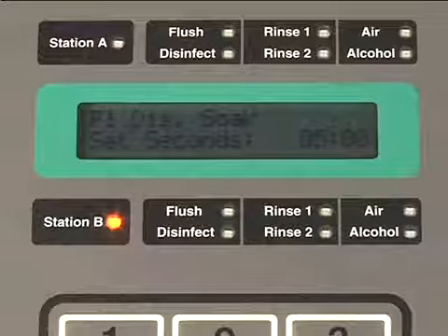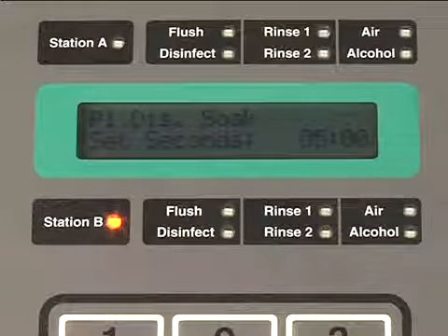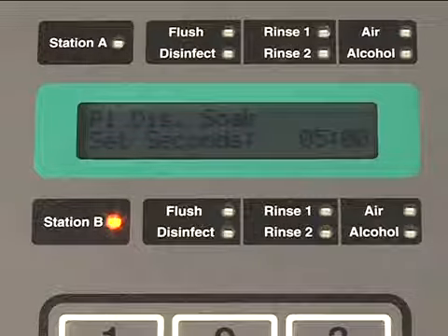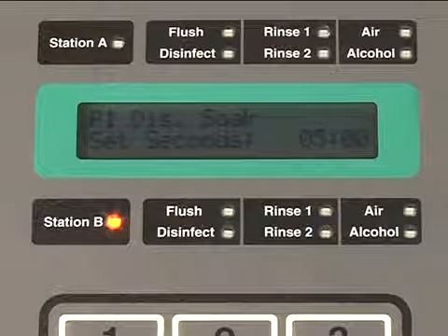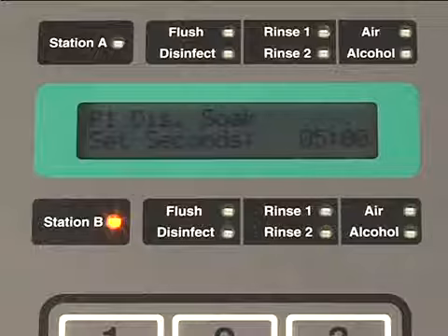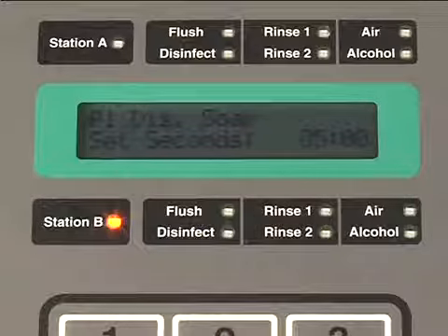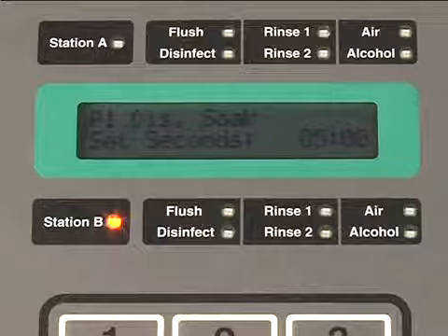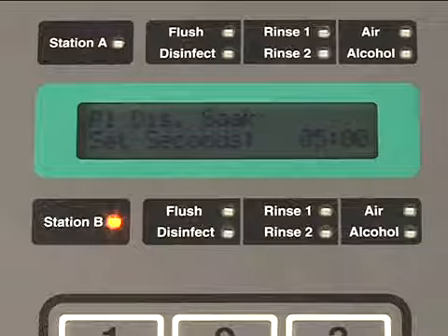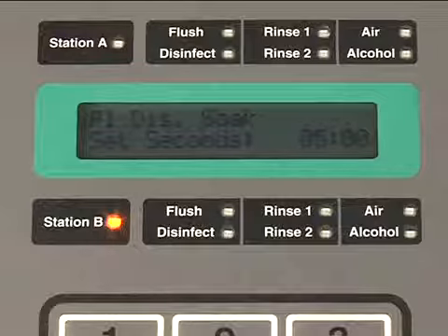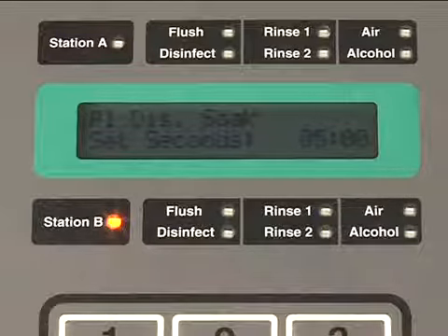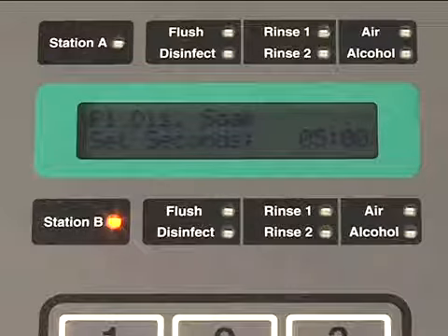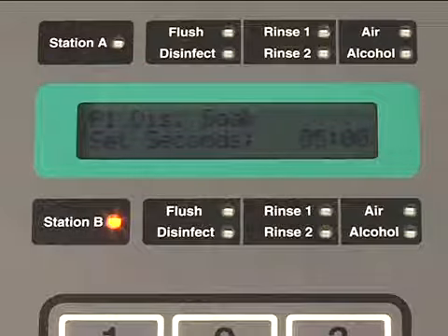The next parameter is the DIS, or disinfectant soak time. This is the time required for the endoscope to soak in the disinfectant solution. For example, Rapicide requires a 5-minute soak time at 35 to 40 degrees Celsius to achieve high-level disinfection. Therefore, we will press 5, then Enter for the disinfectant soak minutes. Press 0, then Enter for the number of seconds.